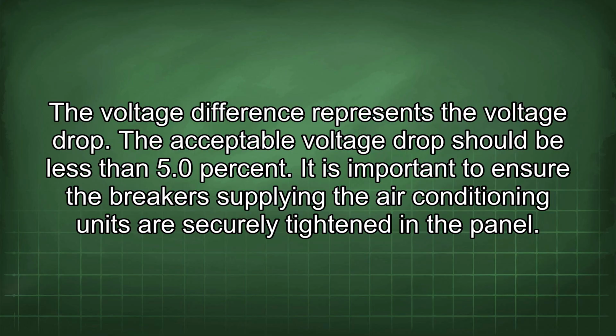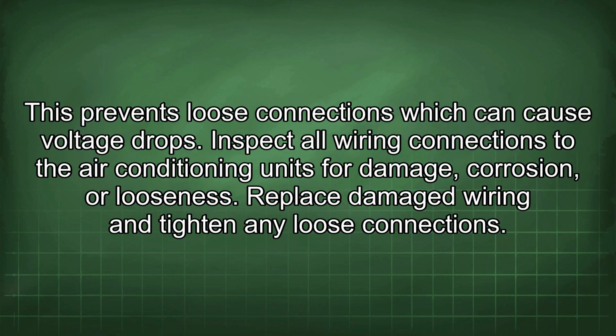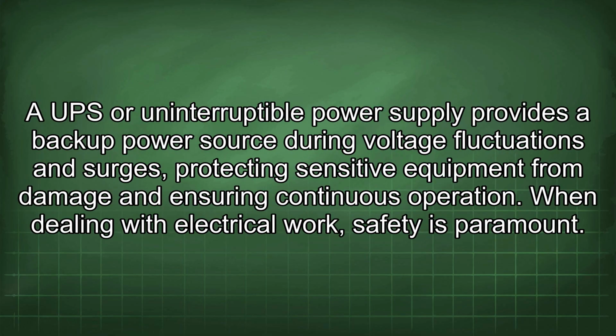It is important to ensure the breakers supplying the air conditioning units are securely tightened in the panel. This prevents loose connections which can cause voltage drops. Inspect all wiring connections to the air conditioning units for damage, corrosion, or looseness. Replace damaged wiring and tighten any loose connections. A UPS or uninterruptible power supply provides a backup power source during voltage fluctuations and surges, protecting sensitive equipment from damage and ensuring continuous operation.